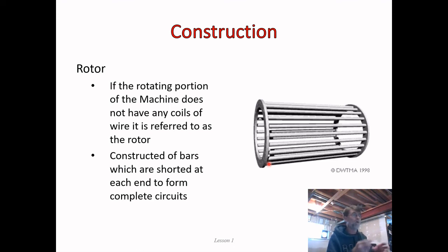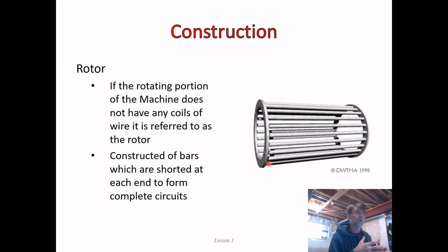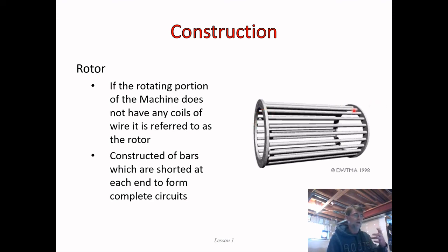This is important because an induced voltage only results in current when you have a complete circuit. The rotor has a whole collection of complete circuits to allow current to flow, and when current flows we get a magnetic field. Since a motor is about the interaction of two magnetic fields, shorting out these rotor bars and allowing current to flow through these short circuits means we get a very strong magnetic field, which is where the torque comes from.